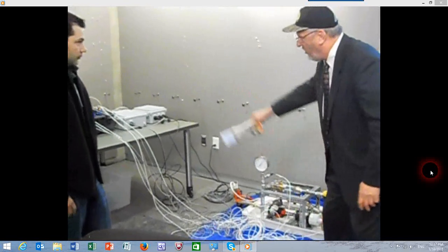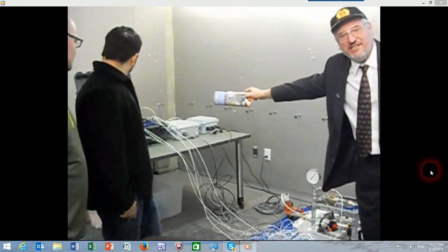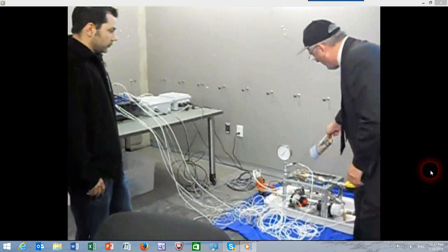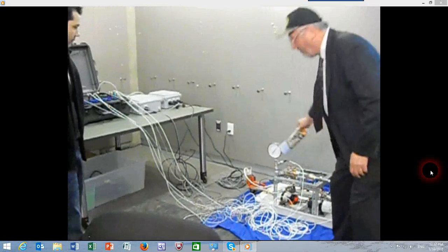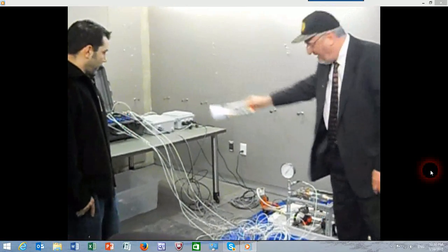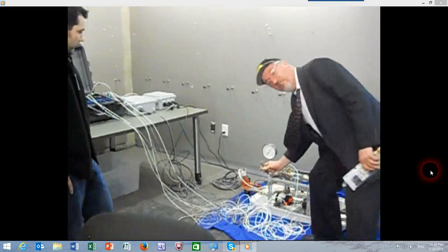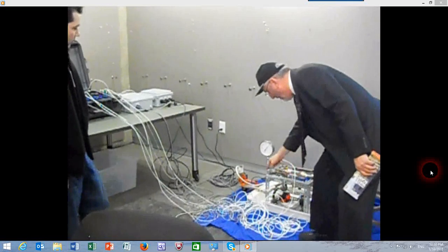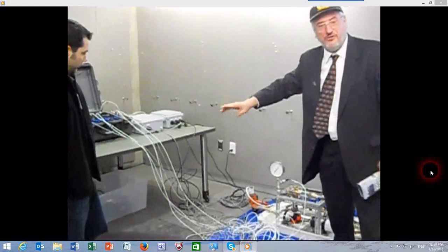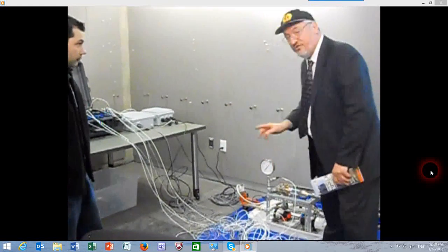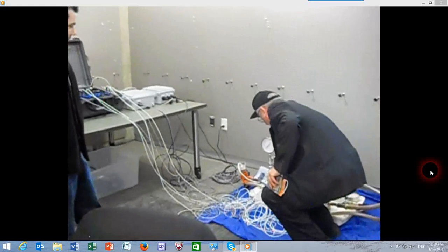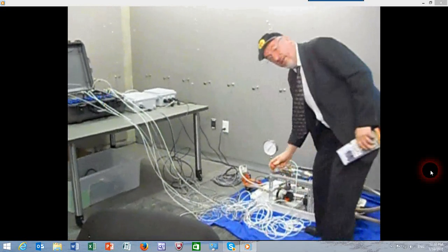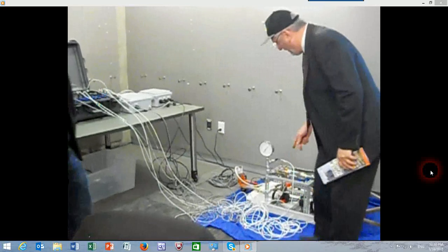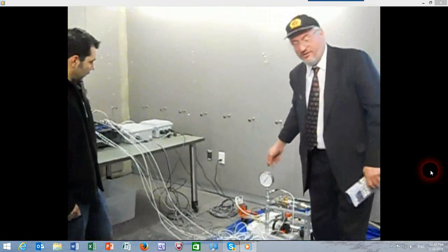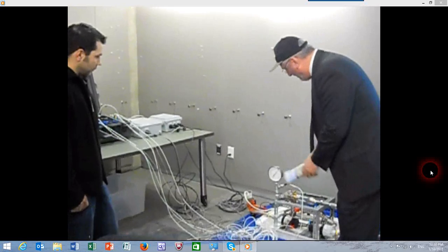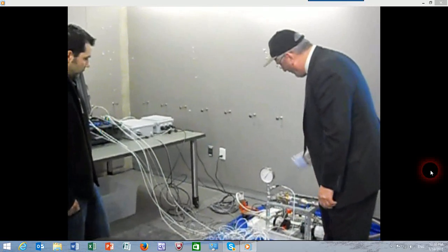So the signal from the flow meter goes to a module we'll call the chassis. Then the pressure transducers on the discharge and the suction of the pump are also sent to the box. Vibrations: here's a vibration sensor, very easily installed, one on the pump, one on the frame, and there's an option to put many more on several pumps. Temperature is red. The magnetic probe is a temperature sensor. We're measuring frame temperature and the pump water temperature in this case. Vibrations, temperatures, pressures, and flow.